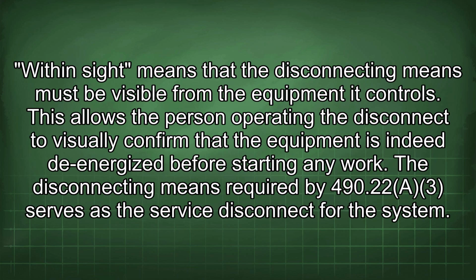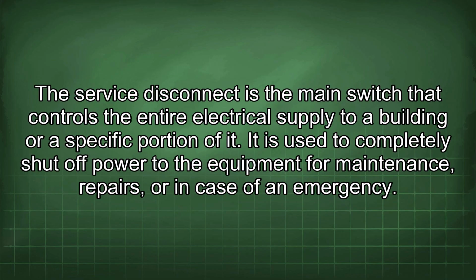Within sight means that the disconnecting means must be visible from the equipment it controls. This allows the person operating the disconnect to visually confirm that the equipment is indeed de-energized before starting any work. The disconnecting means required by 490.22(A)(3) serves as the service disconnect for the system. The service disconnect is the main switch that controls the entire electrical supply to a building or a specific portion of it.